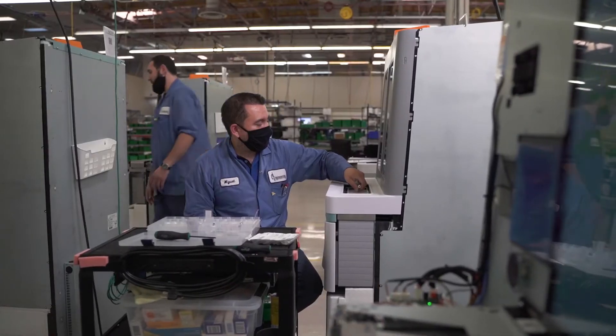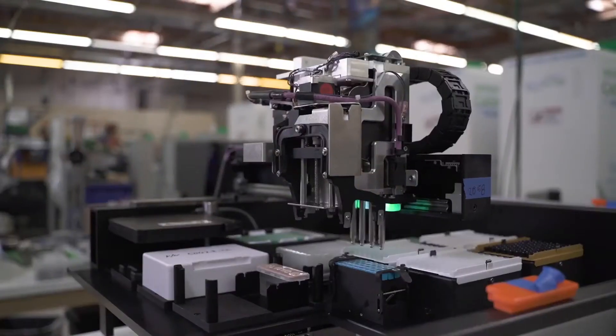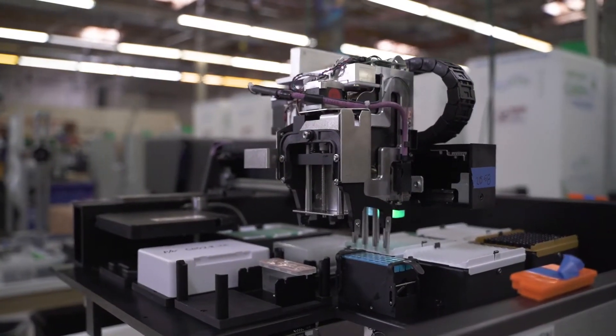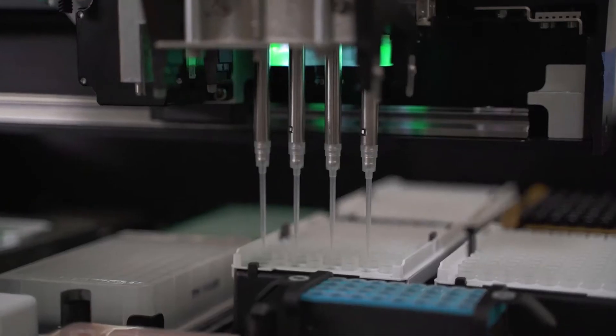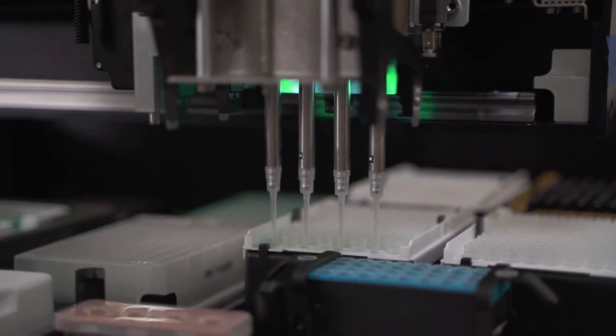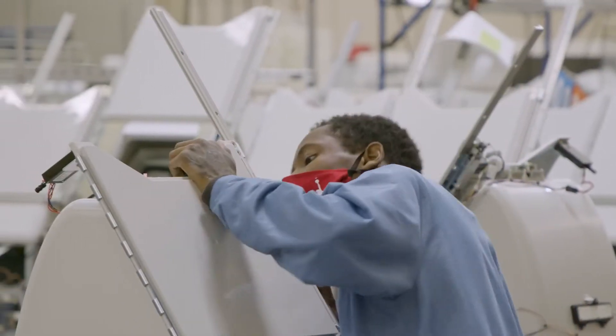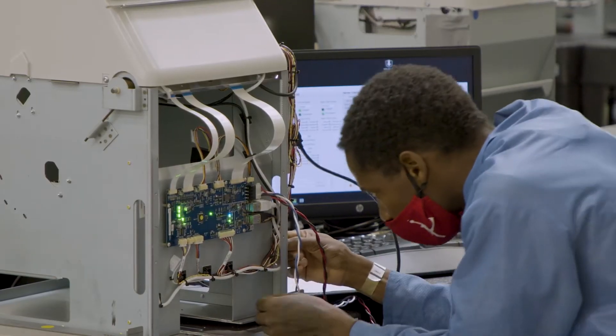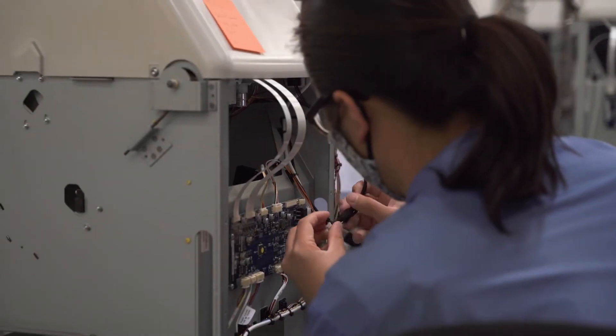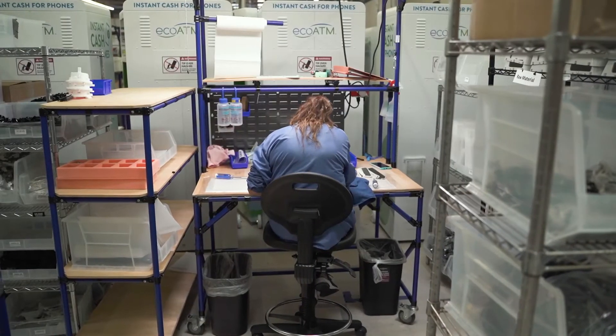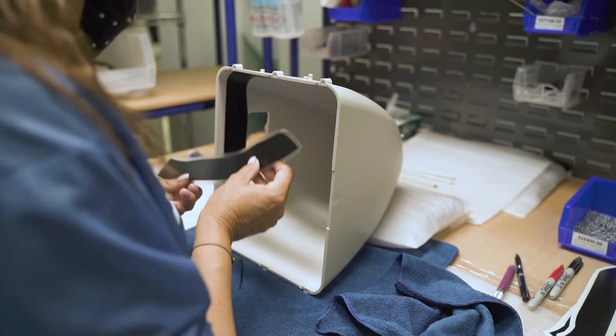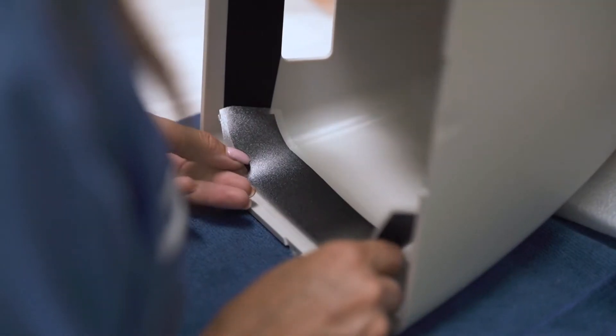One of the interesting things about the medical device or regulated space development and manufacturing process is that if you have a prototyping process that is different than your production process, you have to revalidate and verify your eventual production process. So that really lengthens the overall process and causes the programs to take a lot more time and therefore cost a lot more. Whenever we can eliminate that or shrink that, it's absolutely key to the success of the overall product.